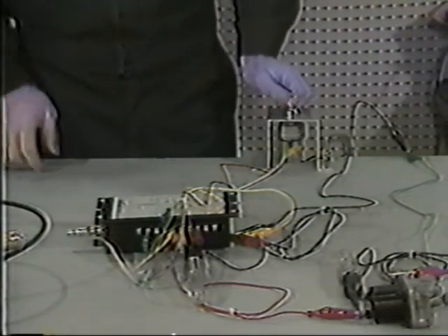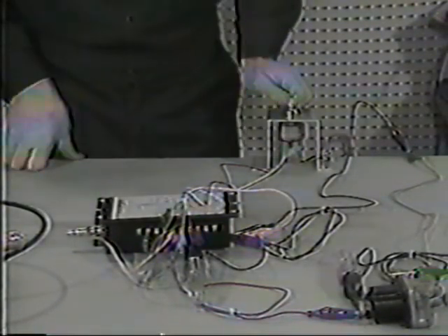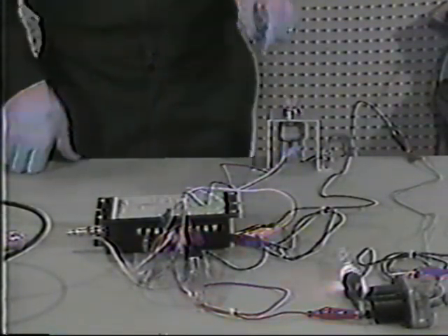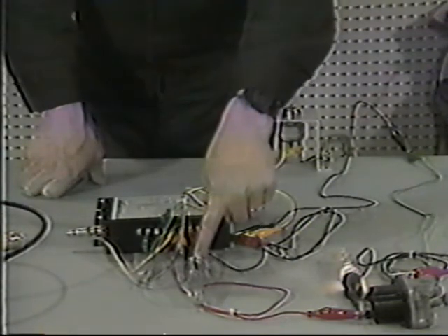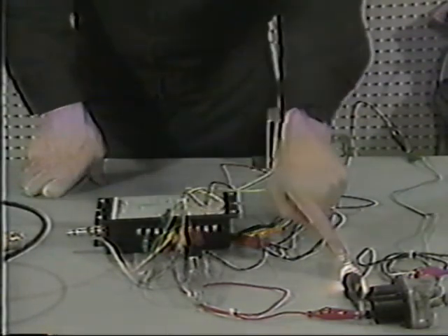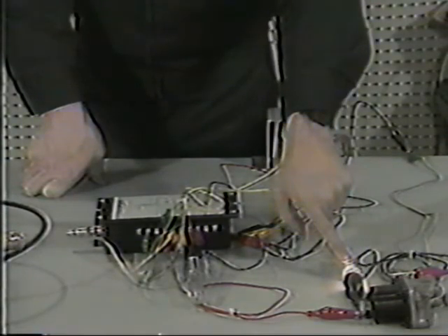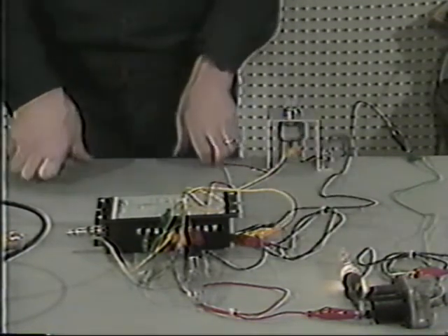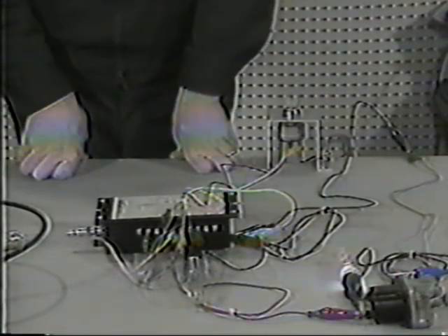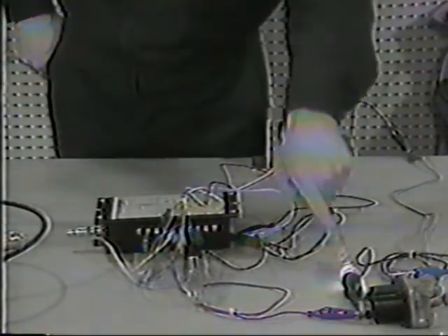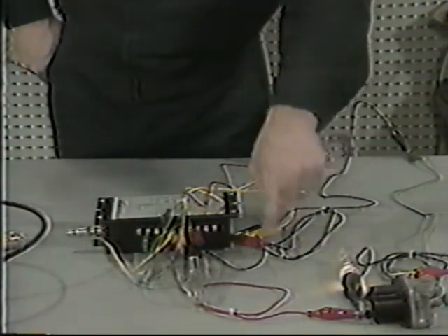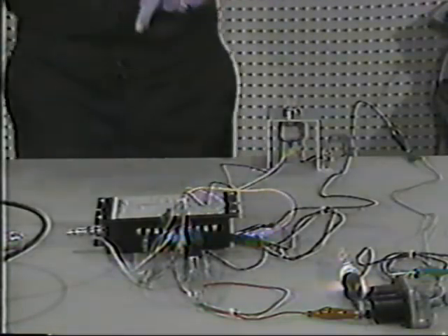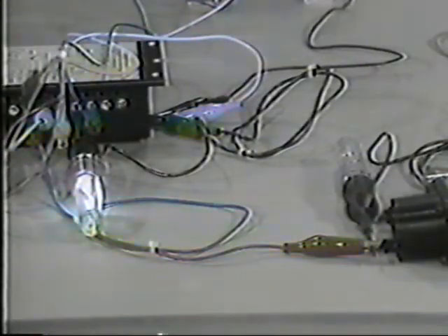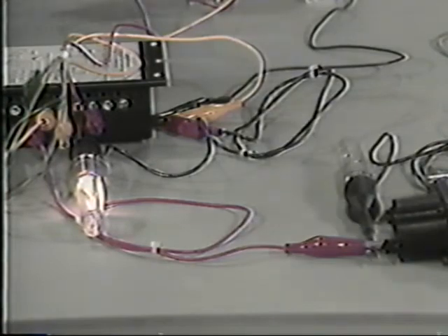Okay. Turn the key on, which will bring voltage up on that key terminal. We should see that this test light, the warning test light, stays off, and the fuel solenoid test light comes on, indicating that the module has turned the fuel on. This situation should remain for approximately 20 to 40 seconds. At the end of 20 to 40 seconds, the fuel solenoid test light should go out and the warning test light should come on. Okay, we passed that test.